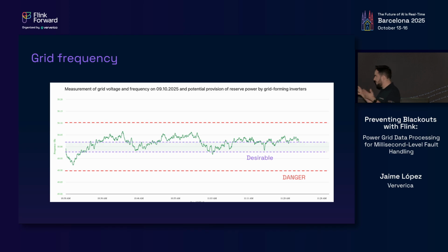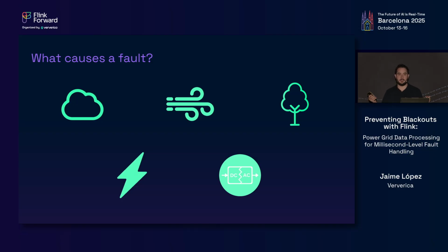And if this gets too out of hand, you end up having an outage. Outages, or faults, sound terrible, but we're prepared for them. Faults are everywhere; faults happen every day. When you're not watching, your TSO is managing faults because a cloud might pass over a solar farm and drop the output by 50% and actually trip it, or you get a sudden gust of wind and your generation goes too high and also trips. A tree that falls onto a power line will also cause a fault. An inverter that fails, lightning striking something. It is an everyday matter. We know how to manage faults as long as we can detect them, correct them and contain them. And containment relies on one and only one thing: speed.